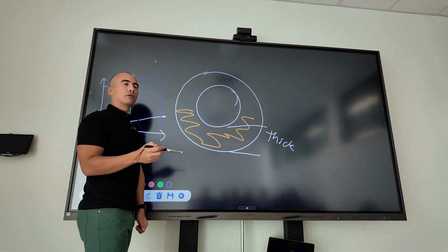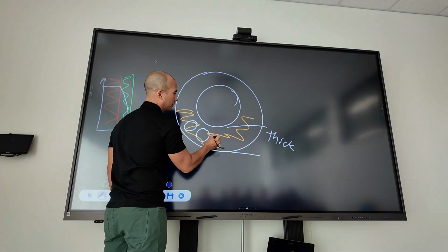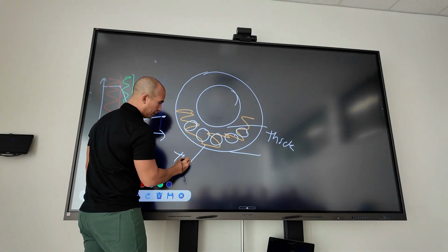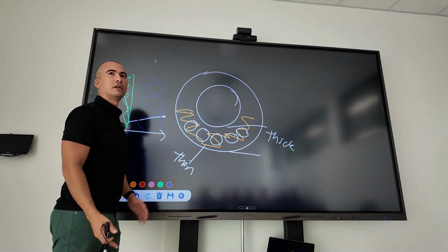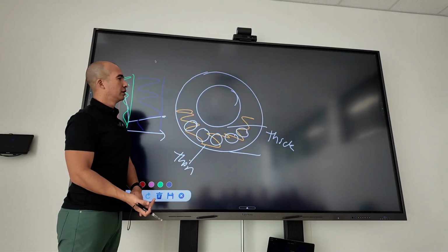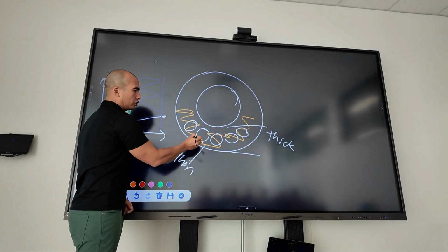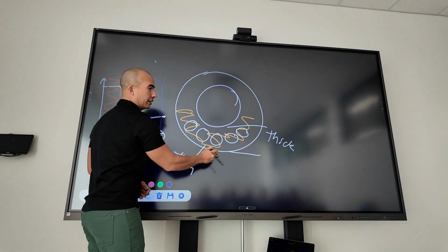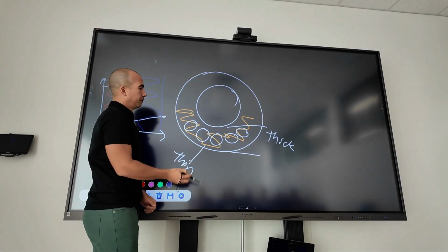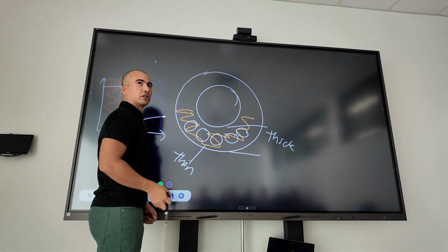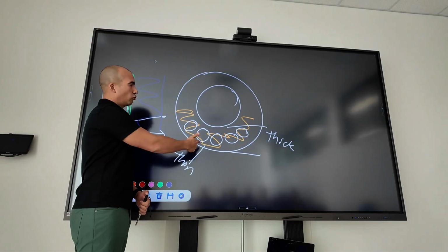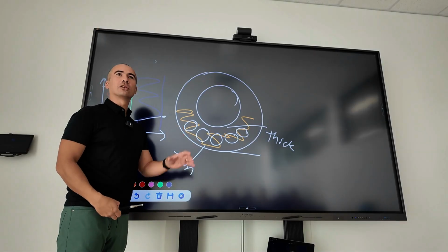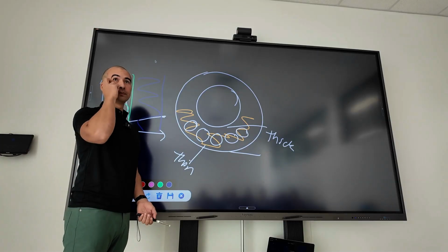If I had, instead, a rolling element bearing, this would be called thin film lubrication, single-digit microns, right? And it's because the surfaces are what we call non-conforming, remember? So that surface and that surface are roughly parallel. This surface and this surface are not. So that's like rolling element bearings, gears, cams would be elastohydrodynamic lubrication. Right?